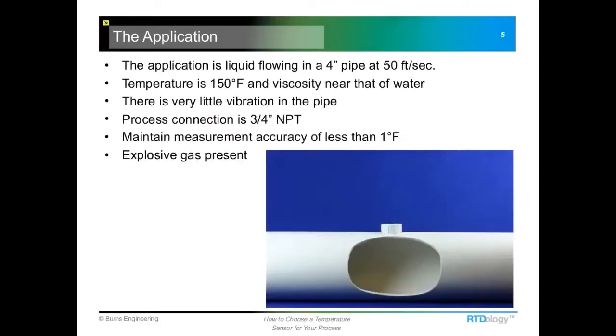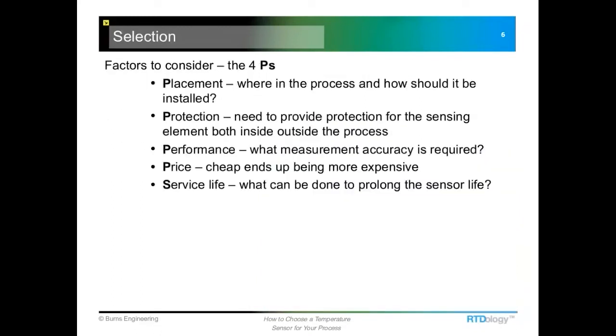So what we're going to do here is look at this application, which we just made up. It's in a 4-inch pipe. We've got some water moving through it, and we're trying to heat it up. And then we've got some explosive gases present around the outside of the process. We have to take that into consideration. There's not really any vibration going on in the pipe, so that's a pretty simple one. We'll step through each of these sections and talk about what to do. I like to divide these up into these categories: placement, protection, performance, price, and then the service life.